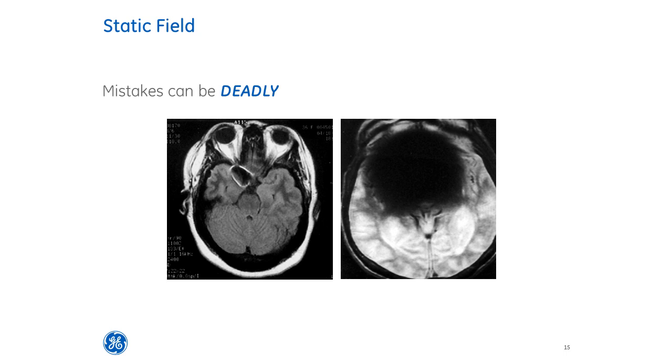As the patient progresses into the magnet, the clip will try to align with the field, and in so doing, puts the very aneurysm that it was trying to protect at risk for rupturing open. There are some MR-compatible aneurysm clips, but make sure you check with the manufacturer to see if those are compatible.